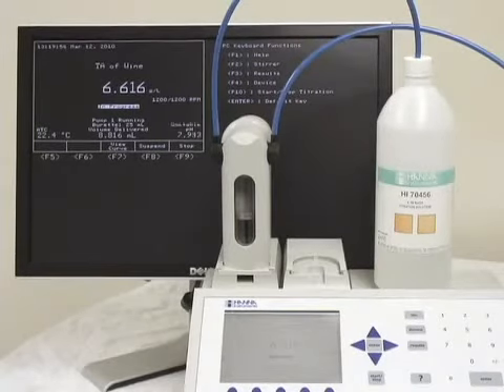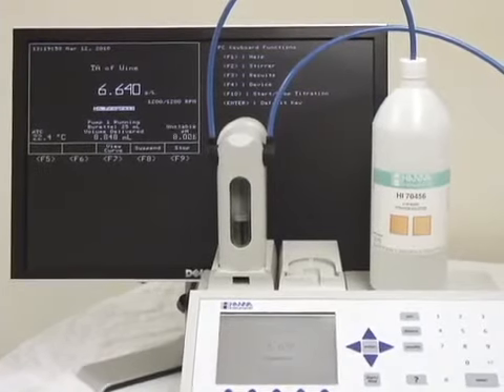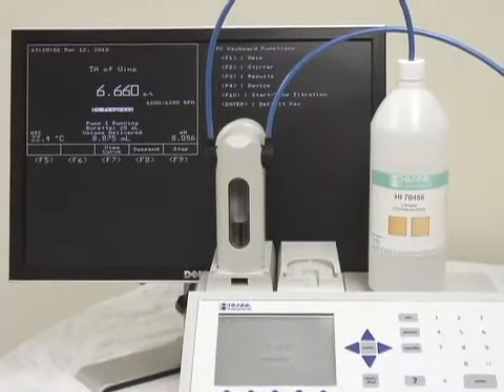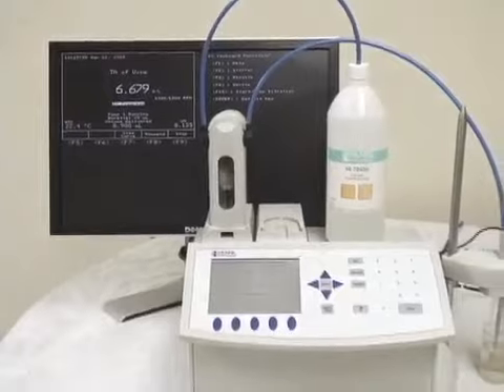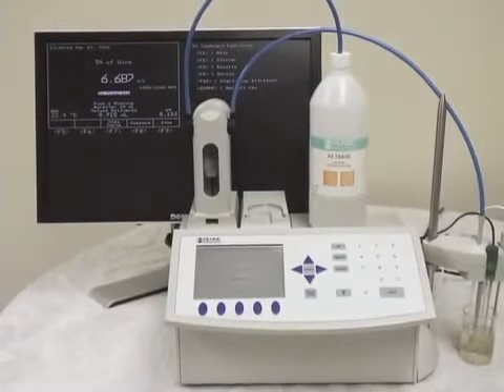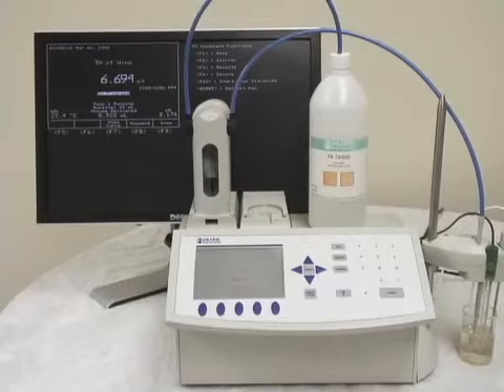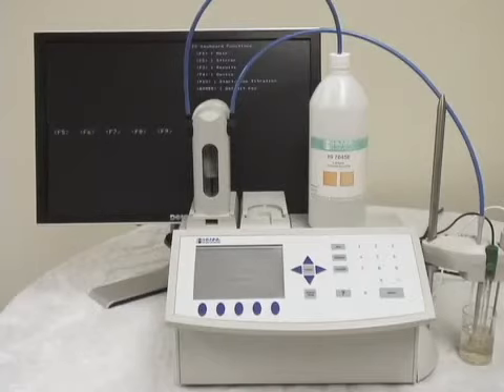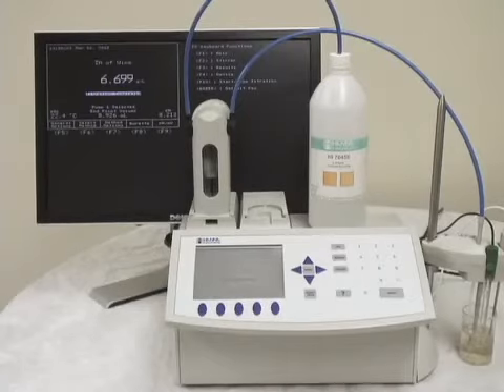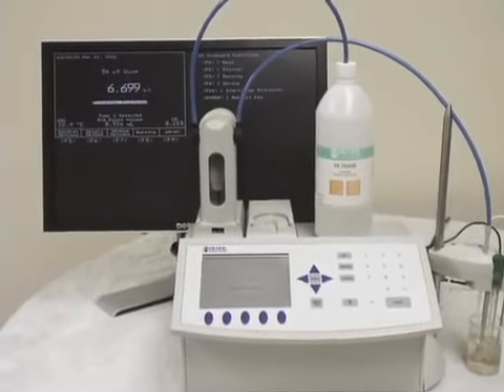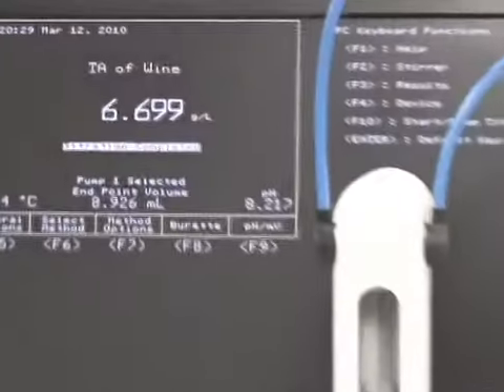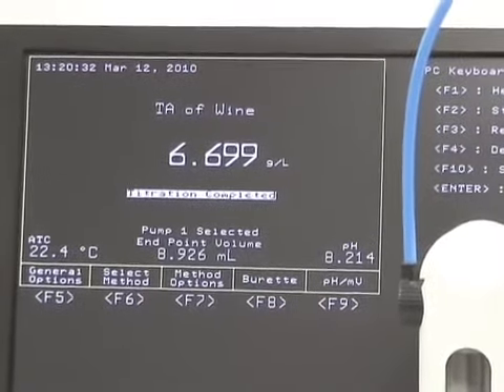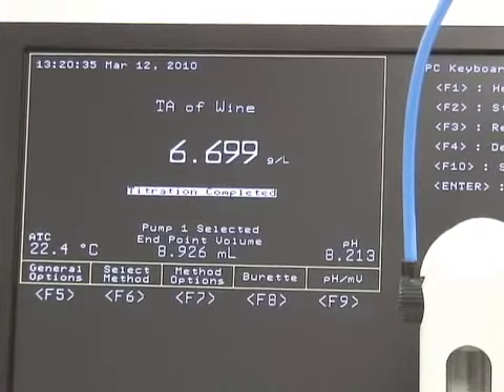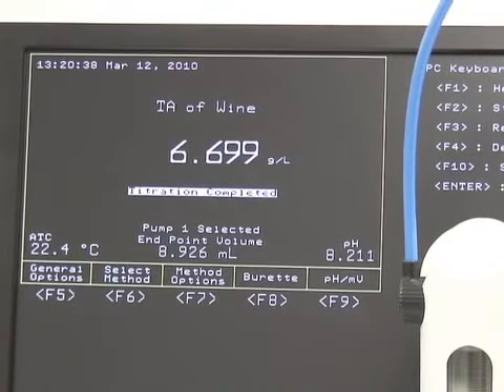Okay, as you can see, we're almost at 8.2, so the machine is going to start dosing very small doses at this point. And there we go, 6.699. We're set at grams per liter right now. You can see you still have your volume at the bottom if you'd like to check your math manually, and your pH. So that's it for total acidity of wine testing. It's a fairly easy test. Thank you, and we're off to our next test.